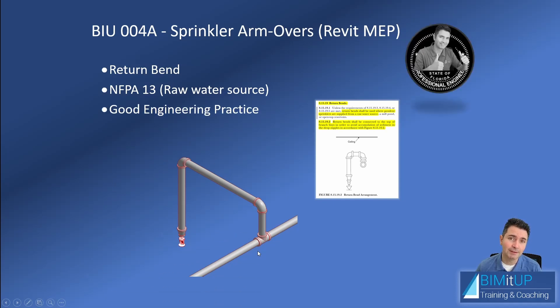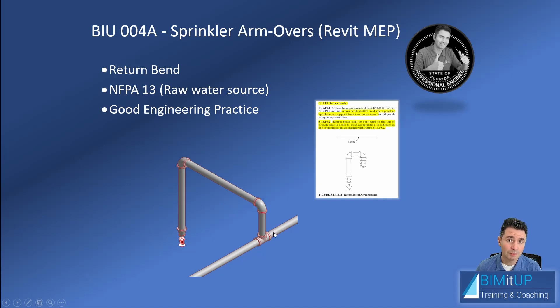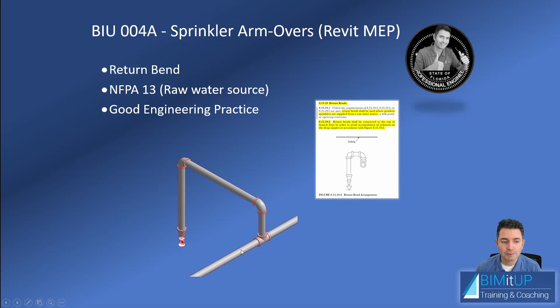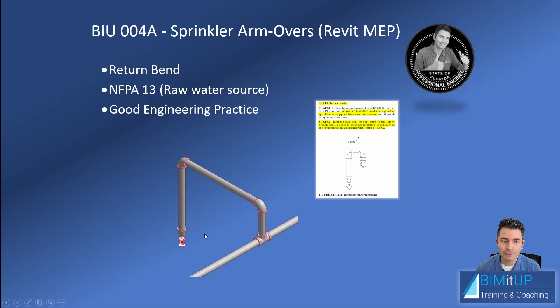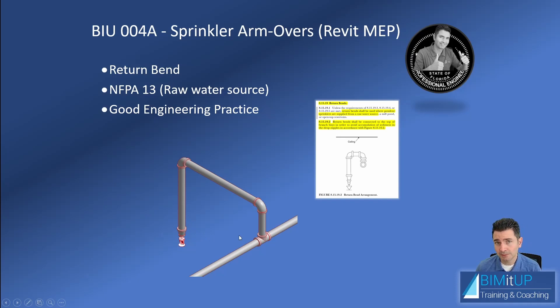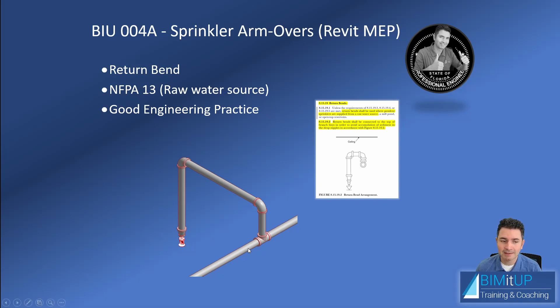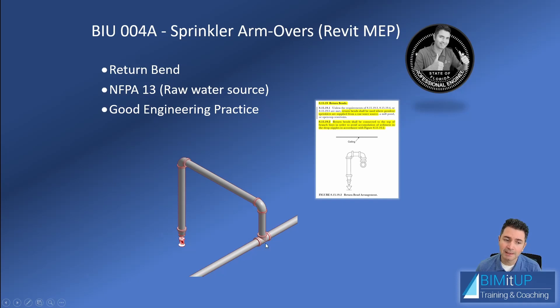That's a very bad practice. Good practice is to provide an arm-over or a return bend for two reasons. First reason: you have accumulations over time of sediments like dirt and sludge because this is sitting water, this is not circulating. Hopefully it's only circulating if you have a sprinkler operating because you have a fire, but in your typical situation, your best case scenario, this is stagnated water.